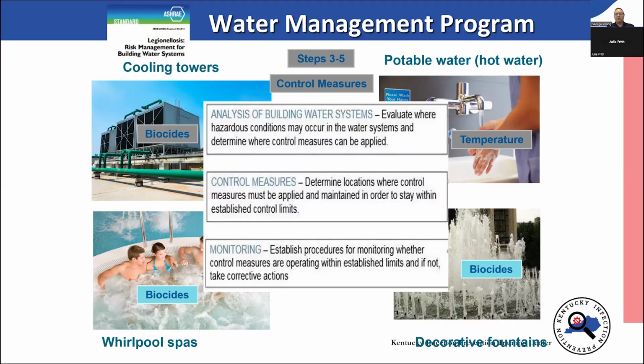You're going to use chemical biocides. This is where your water treatment provider comes in and provides that knowledge and expertise. We've seen biocides are typically more effective when used in a multi-stage program, with a continuous feed and an individual slug feed that helps minimize biofilms and areas of proliferation for Legionella.